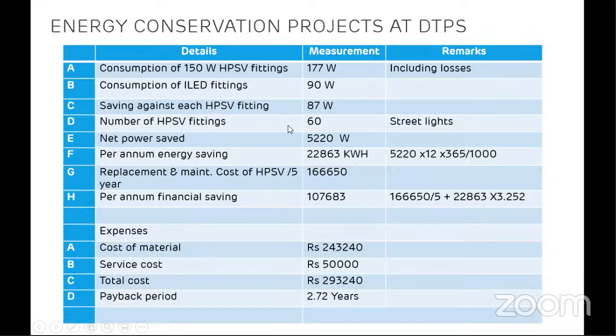There are 60 street light fittings having sodium vapor lamps. The power saved was 5,220 watts. The per annum saving came out to be 22,863 kWh or units. The replacement cost was 1,66,000 rupees, and the per annum financial saving was 1,07,000 rupees. So just by replacing 60 sodium vapor street lights with LED lamps, we saved 1 lakh rupees per annum. I also have to consider the expense of installing these new fittings.